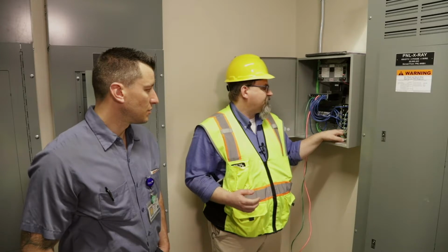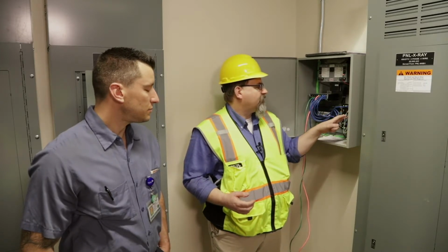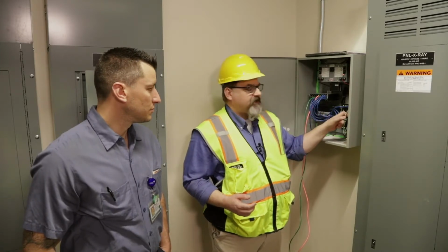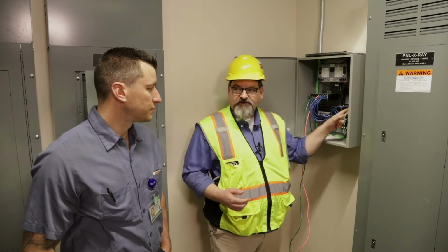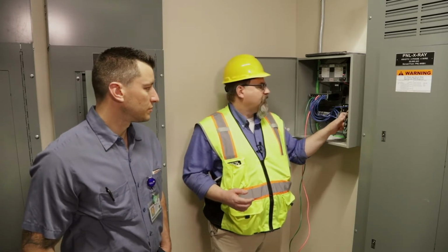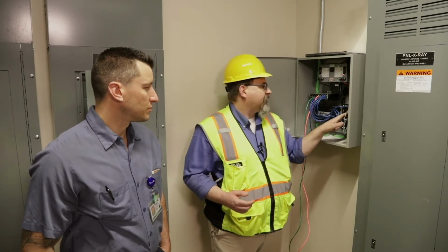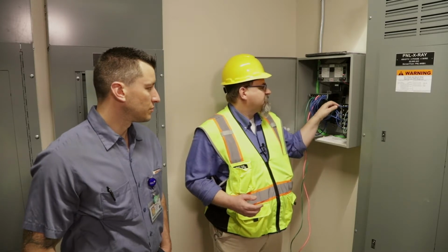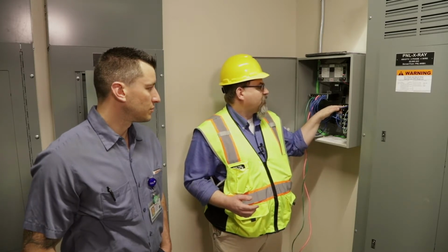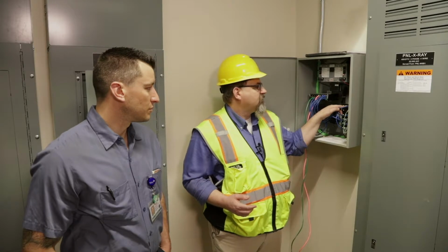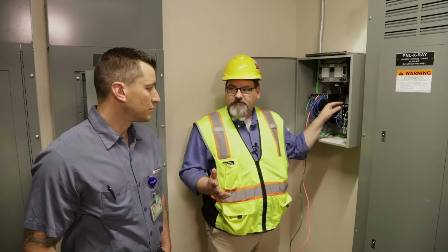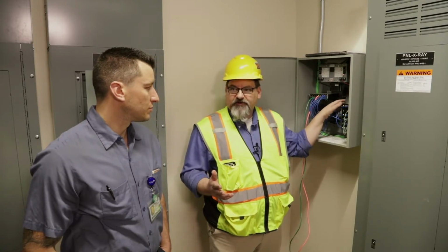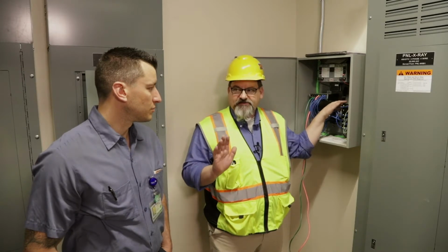All right, so the MSTP, you can see the little green light going off, this is the 5th floor here. There's no wires to that because there's no bridges or rooms up there. And of course, you don't see any MSTP traffic. If you see this freeze, either on or off and never change, we may have just accidentally caused a fault on the system and it just kicked it out and said stop.